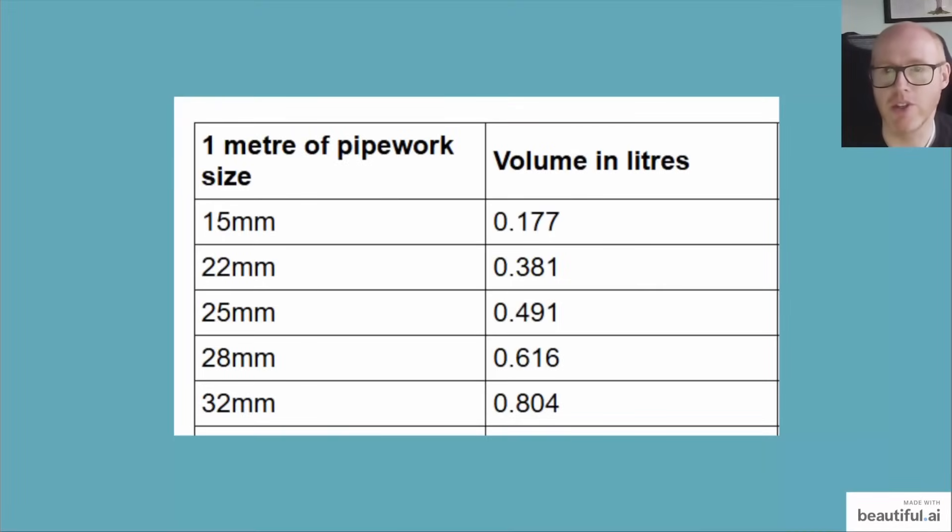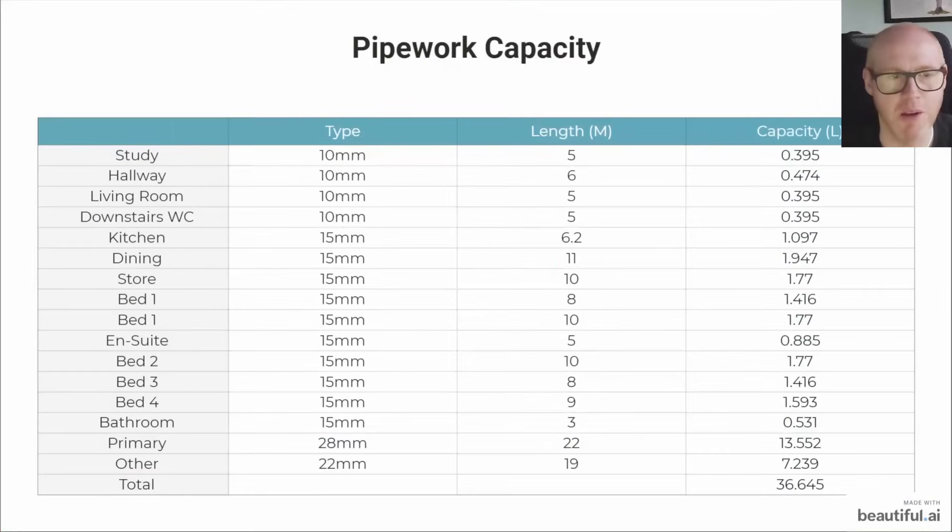To do that you will need to use tables like these. You can find them everywhere. Finding it for 10 millimetre was a bit more difficult, but we did find one in the end. You can see that one metre of 28 mil pipework has 616 millilitres, so quite a considerable amount. Maybe those long pipework runs from a heat pump to a home, maybe they're not such a problem after all if they can boost our system volume. An interesting thought for the installers and engineers to think about.